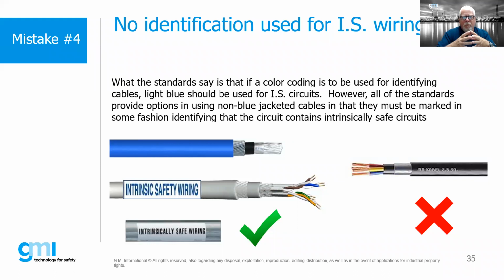So, mistake number 4, no identification used for the IS wiring. As we mentioned, you can use light blue as a cable color if we're going to use color coding. However, we can also put tags and we can put sleeving on it. We can do many different things, but we have to mark it. We have to say that this cabling is housing intrinsically safe circuits, or conduit, or however we're doing this.